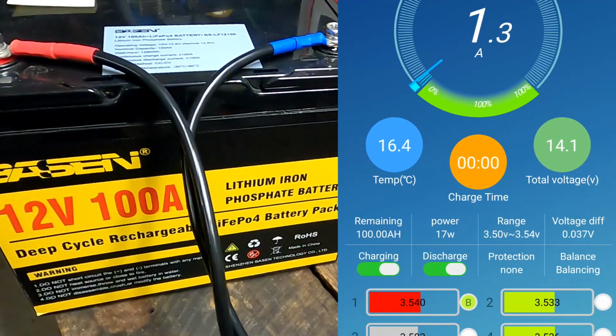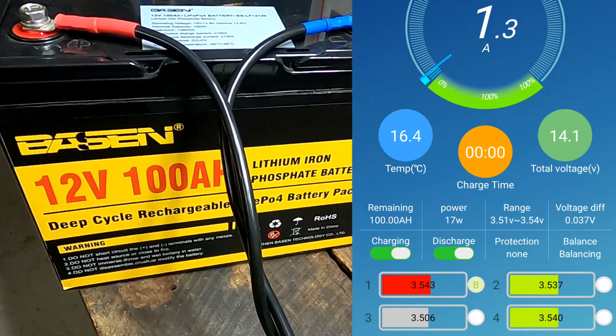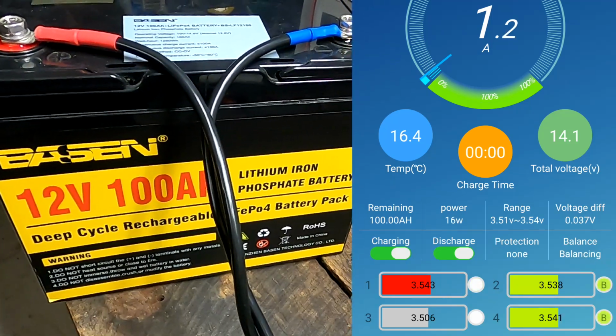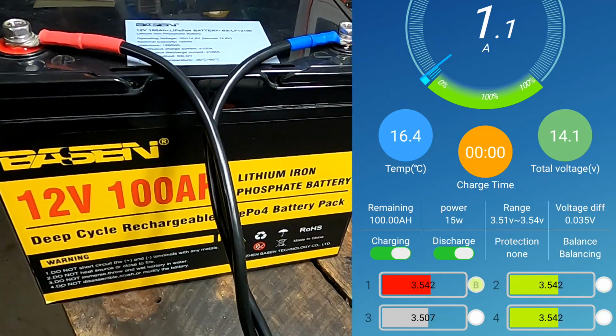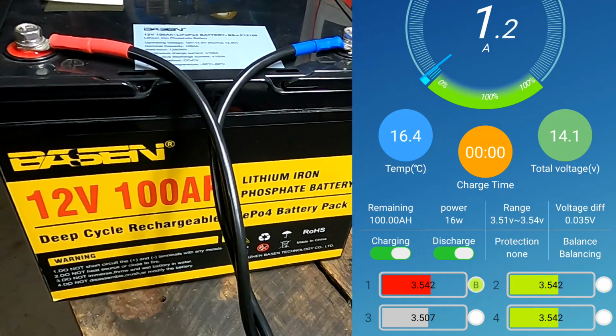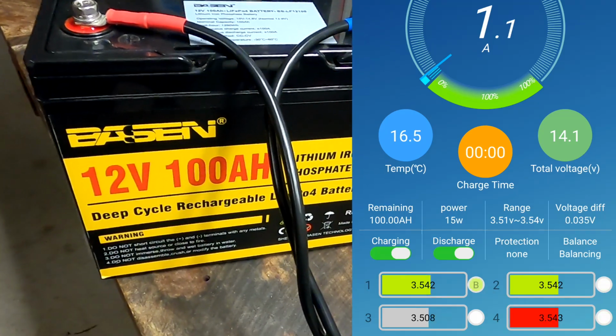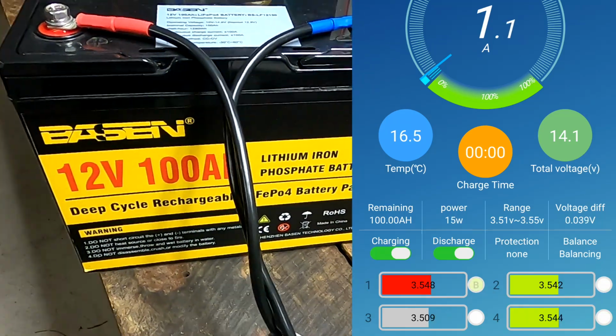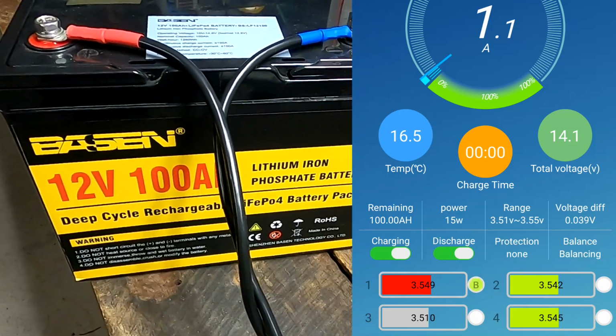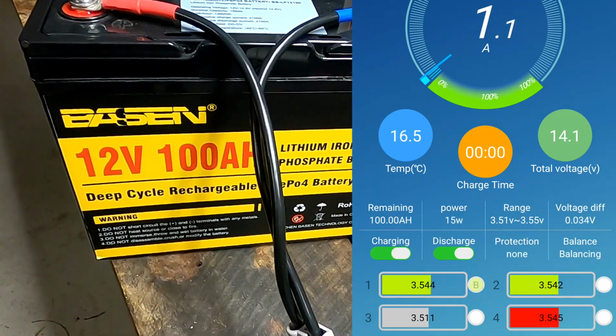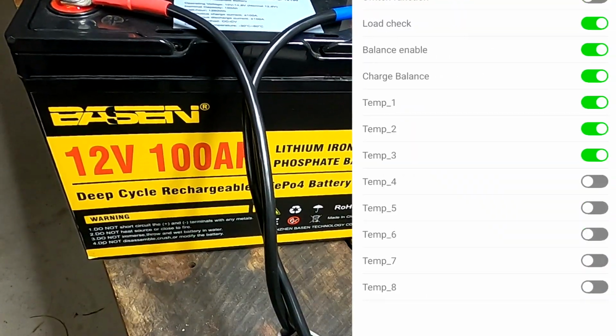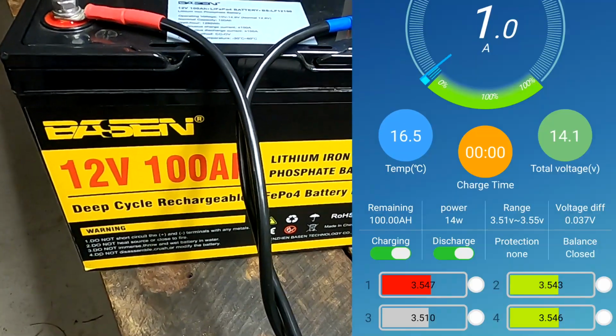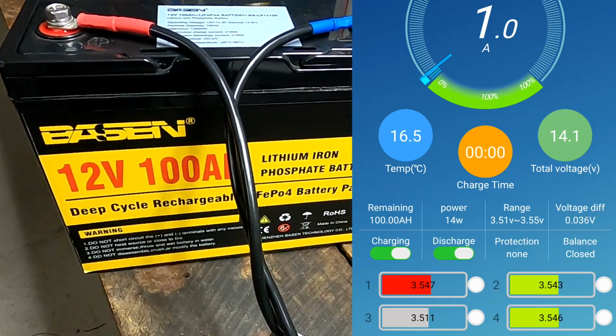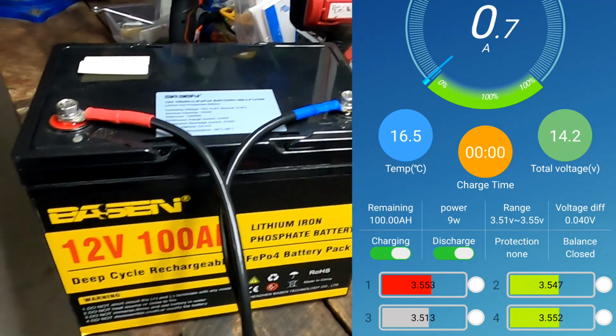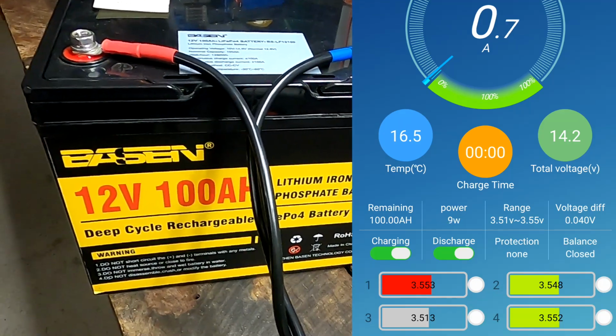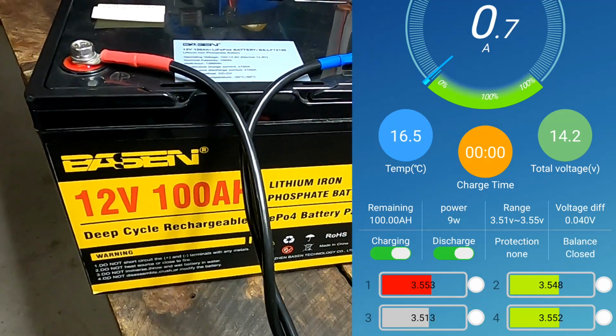What this does is basically it only balances the battery while it is charging. And the threshold here to start balancing is at 3.4 volts. Then the internal balancer of the BMS kicks in and starts balancing any cell which is over 3.4 volts. So if I go here and turn off charge balance, you will see, look at this, there's no balancing happening anymore. So you can have only balancing while the battery is not charging, or balancing while the battery is charging.